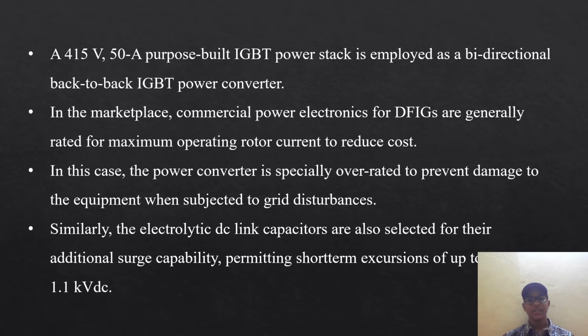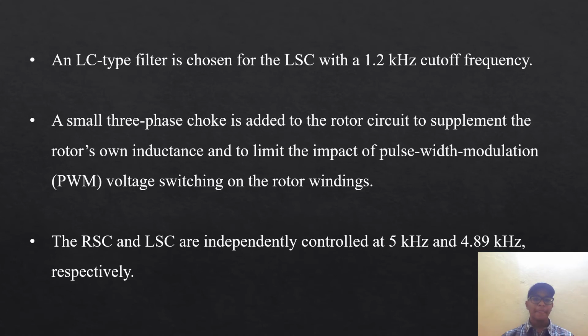Similarly, the electrolytic DC link capacitors are also selected for their additional surge capability, permitting short-term excursions of up to 1.1 kVdc. A small three-phase choke is added to the rotor circuit to supplement the rotor's own inductance and limit the pulse width modulation voltage switching on the rotor windings. The RSC and LSC are independently controlled at 5 kHz and 4.9 kHz respectively.